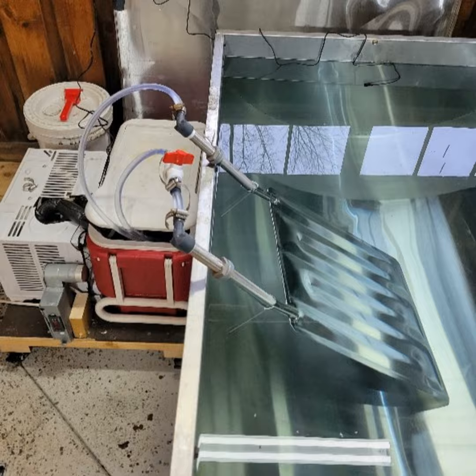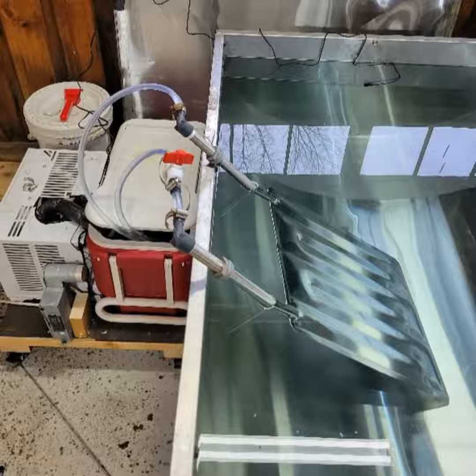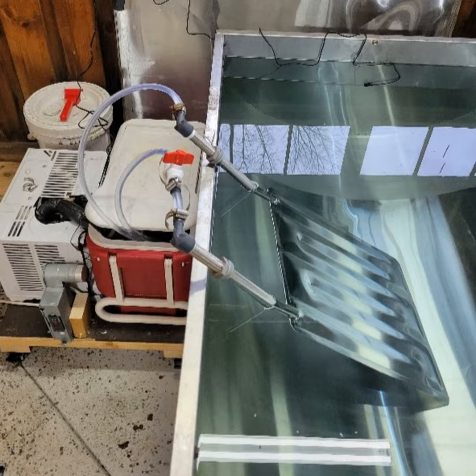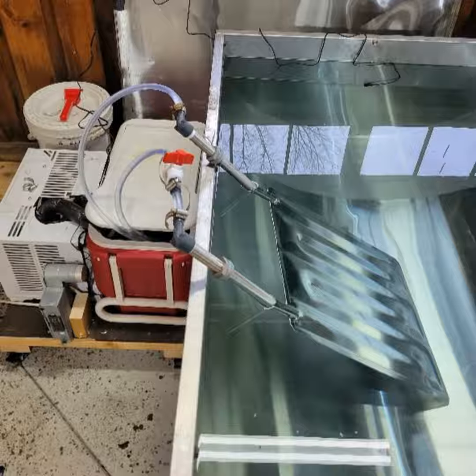Yep, I agree completely. One thing I want to note about these window air conditioners, as I mentioned earlier, the BTUs is the capacity of how much heat they're able to remove to cool down a solution. And when you buy these glycol chilling units, they'll be rated for a certain amount of BTUs per hour, and you should be looking for what temperature they chill down to. So is it rated to chill at 50 degrees, or is it rated to chill at 20 or 25 or 28, which are going to be very different. And so you want to make sure it's going to be rated for around what you actually want to chill for.